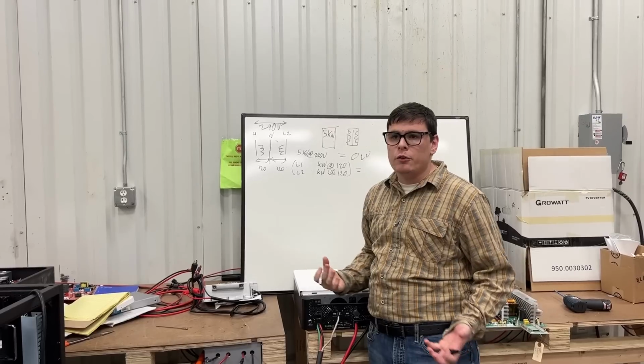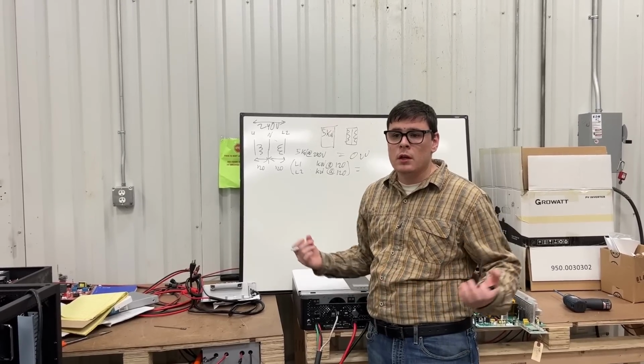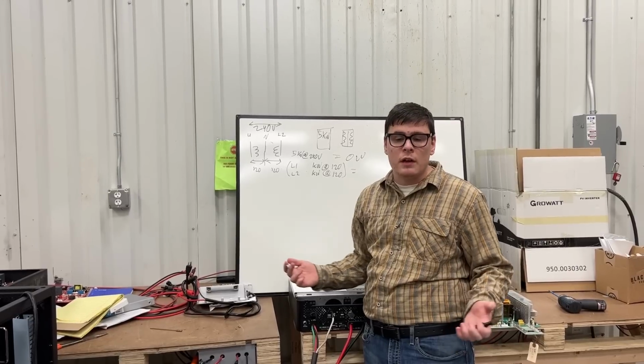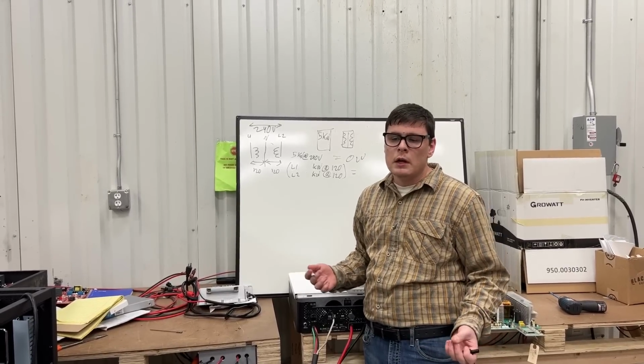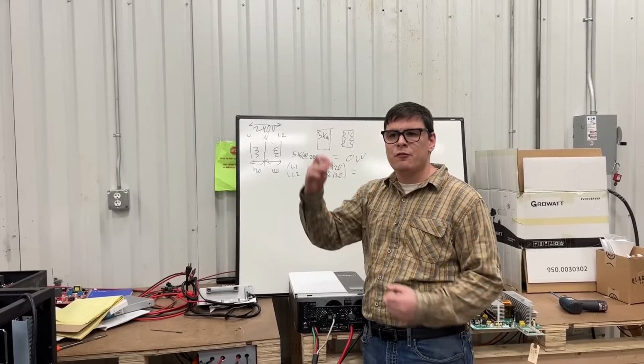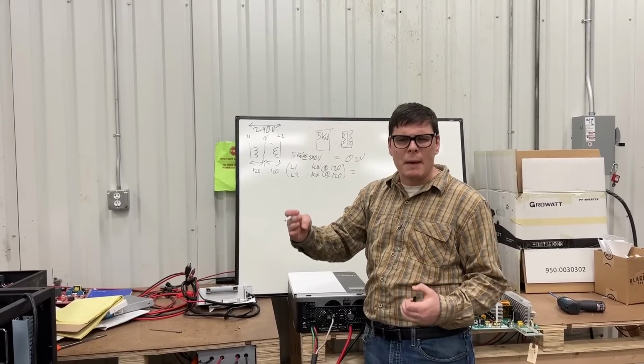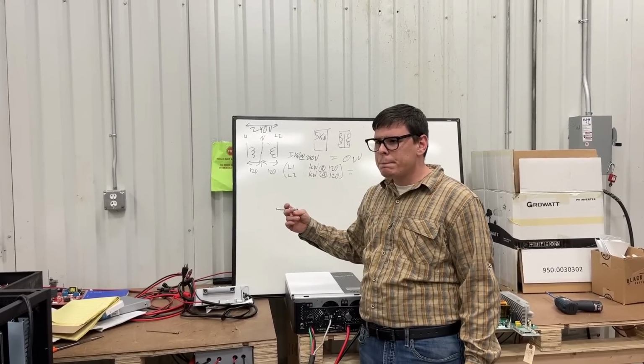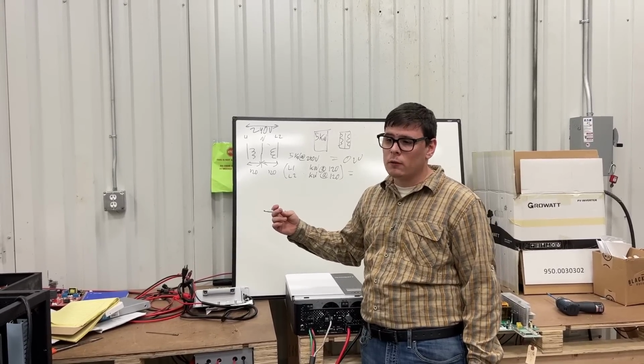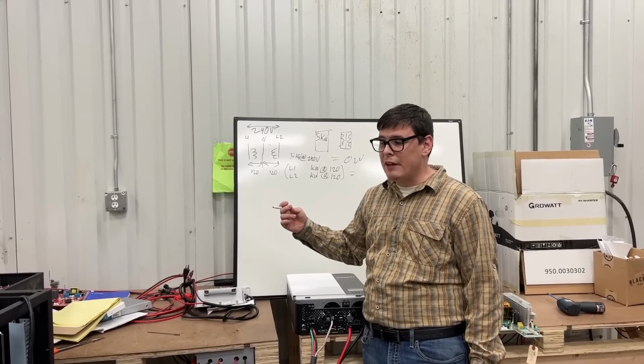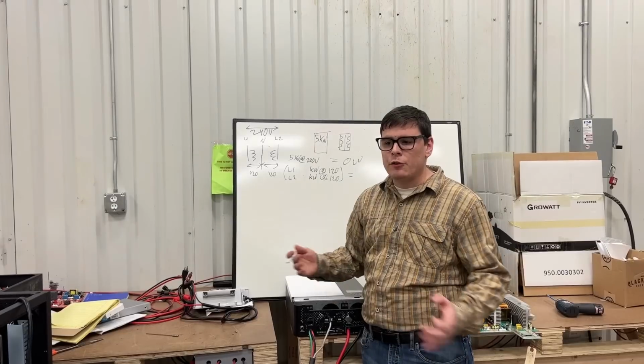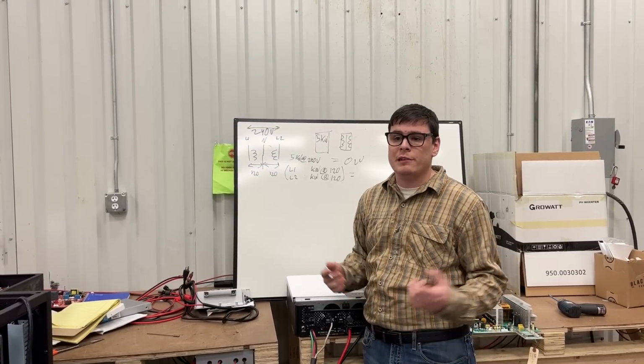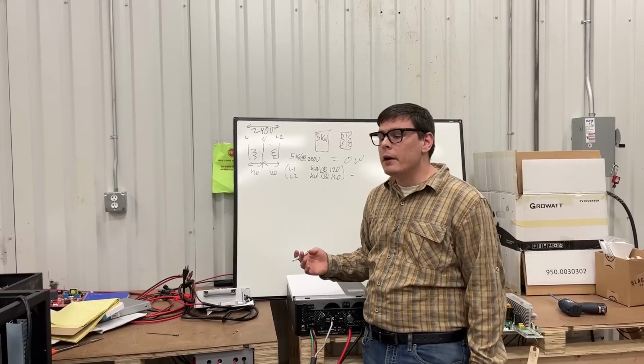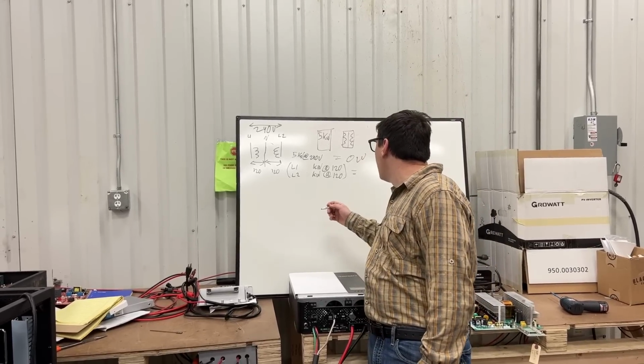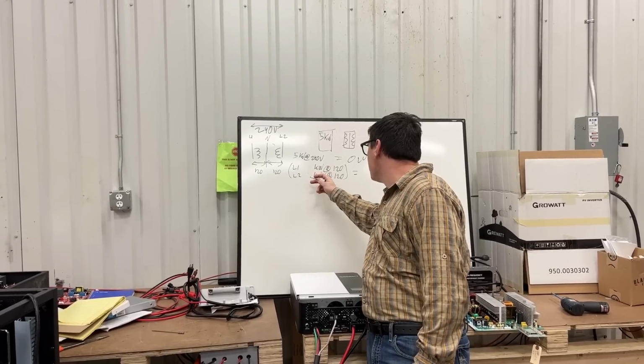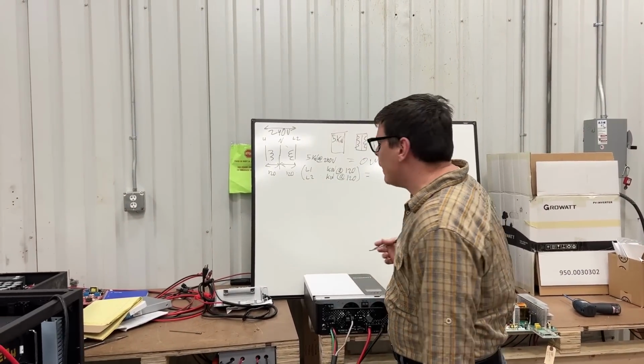Again, you look at your load sheet, and if you have 5 kilowatts of 120 volt loads and you intend to balance them, you can get away with a 5 kilowatt transformer. You intend to balance them with some degree of reason. Again, that 4 to 1 is still within range on a 3 kilowatt imbalanced transformer. If you have a 5 kilowatt transformer, and you have less than 5 kilowatts of load, then that transformer is fine. If you're going to have more than 5 kilowatts of 120s, which, by the way, I'd like to know why, then a second transformer would be necessary.